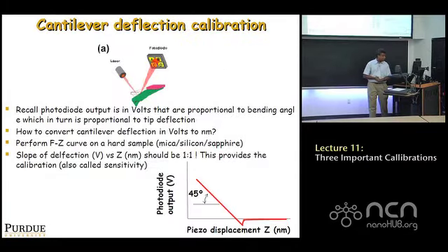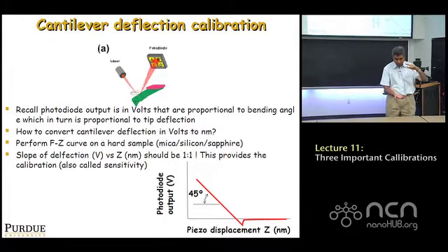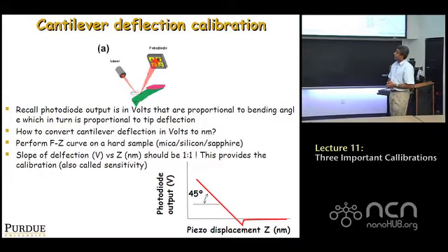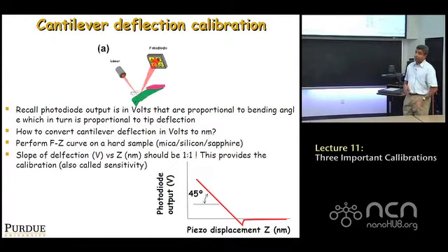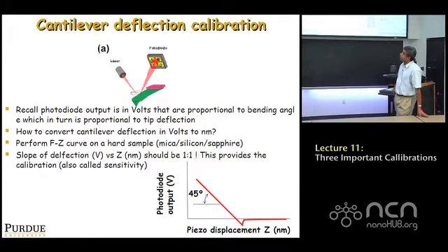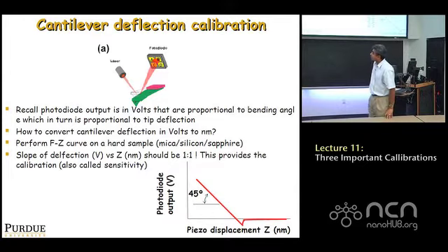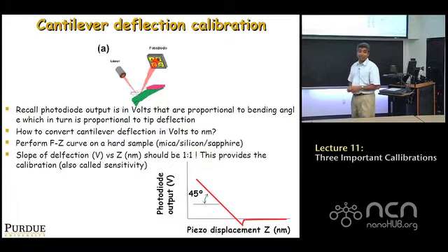Okay. The second is the cantilever deflection calibration. So as shown in this figure, what is happening is when you press on a sample, the cantilever bends, and the bending angle is measured as a voltage output from the photodiode. What we need to do is to convert the voltage output to the up and down motion of the tip, the deflection of the tip in nanometers. Okay, that's what we have to do. How do we do this? The standard way of doing this is to do what's called an FZ curve on a hard sample. By the way, this conversion has to be done even if you have a closed-loop piezo. This has nothing to do with closed-loop piezos, okay?